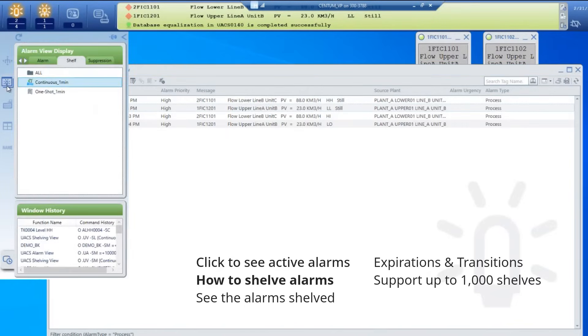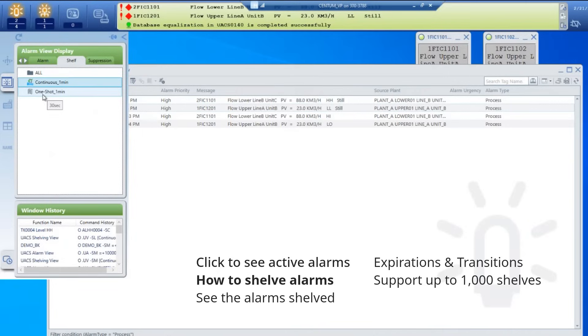I can look at the shelf. I have two shelves here: a continuous one-minute shelf and a one-shot one-minute shelf. One-shot shelves will recover and go back to the main alarm page once they transition back to normal. A continuous shelf will stay in there as long as the designated alarm shelf time period has not expired.